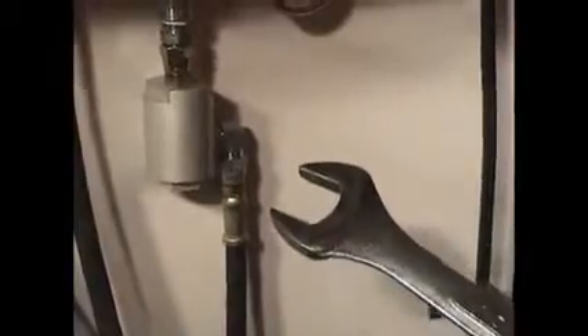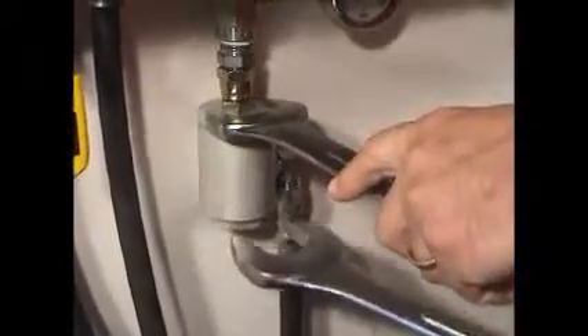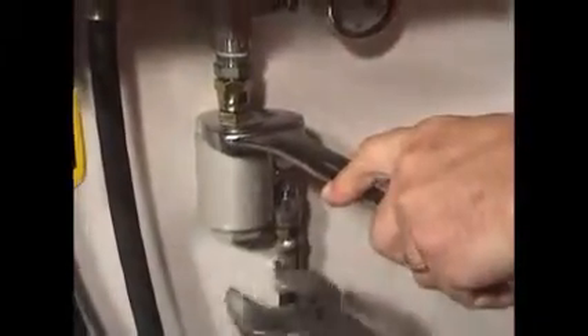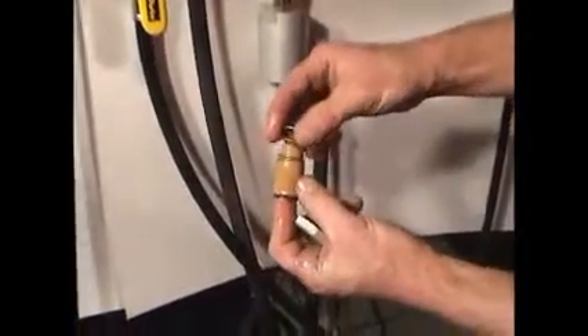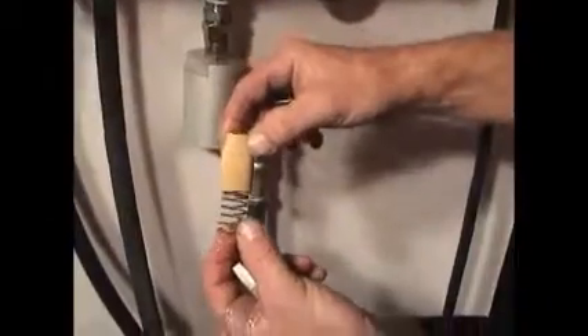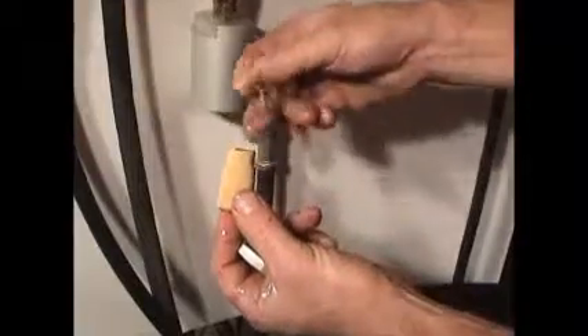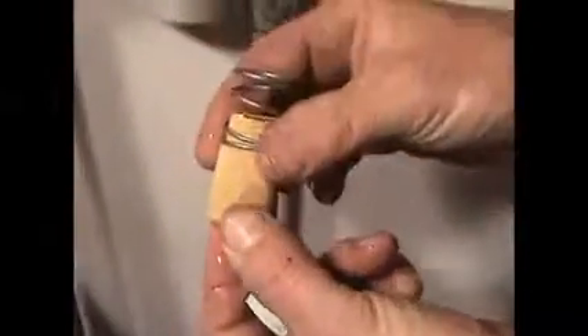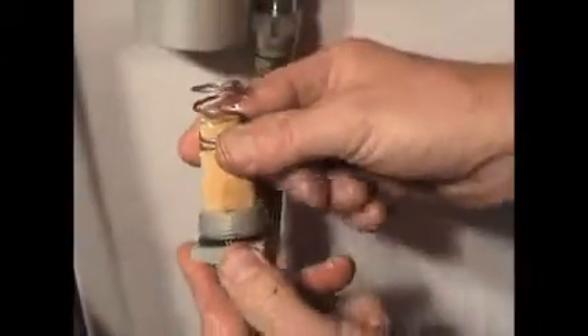Changing of the filter element can be performed by using 2 wrenches, a 1 3/8" wrench on the top side and a 1 1/2" wrench on the bottom side. Remove the filter housing. There is a spring on the outside of the filter. There's also a spring on the inside of the filter. Remove those. Install a new element by inserting the spring back on the inside and the spring on the external side. Mount it back on the cap.